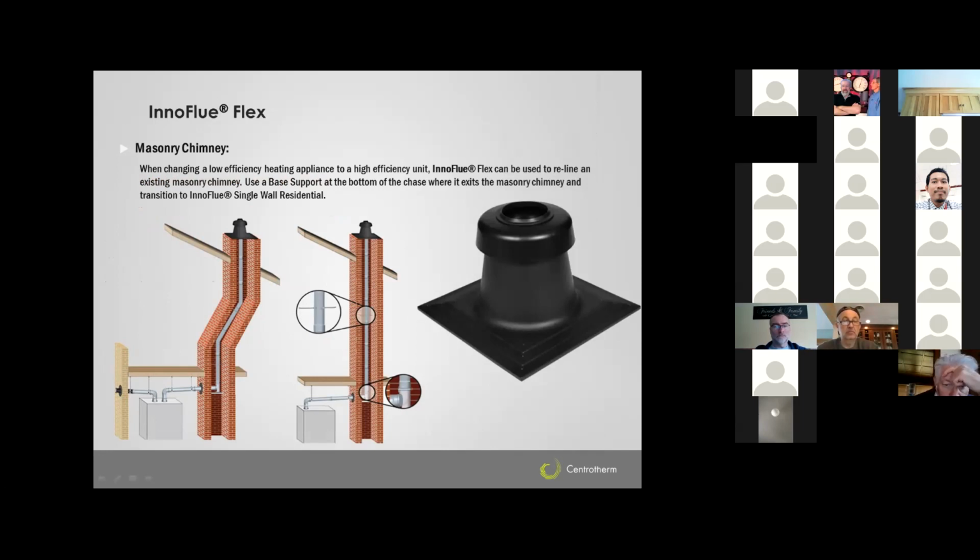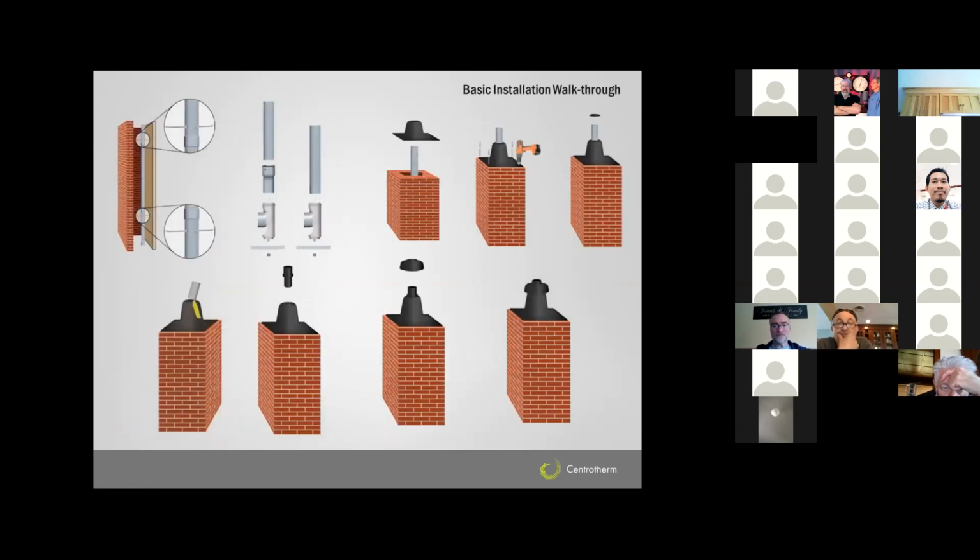And here we're just highlighting, this would be a chimney cap that they manufacture. They do manufacture it, and it's specifically to seal the top of that chimney. They have standard units, and they make custom quite often. A quick note to make is whatever the distance is to get to the high point of the top of that chimney, they always say add an additional 2 feet of the pipe, and that's to support the chimney cap that's going to be installed.